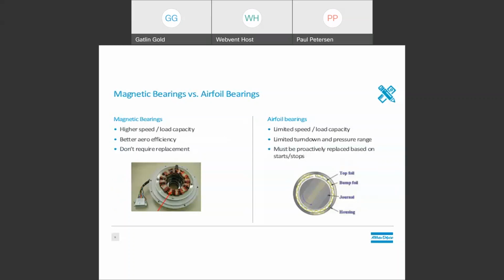Here's a look at the non-contact bearings I talked about in the previous slide. Instead of using oil like traditional contact bearings, ball and roller style, these bearings use either electromagnetism or fluid dynamics to levitate the shafts and prevent contact between shaft and housing, eliminating the need for oil. We see these in high-speed turbo applications. Magnetic bearings were introduced in high-speed turbo blowers first. They came in the 1990s from European manufacturers. This technology can be constantly levitated and actively controlled to prevent contact in almost all situations. Because there is active control of the shaft position, these blowers are more resistant to surge, giving them a wider range of operation or more turn down.